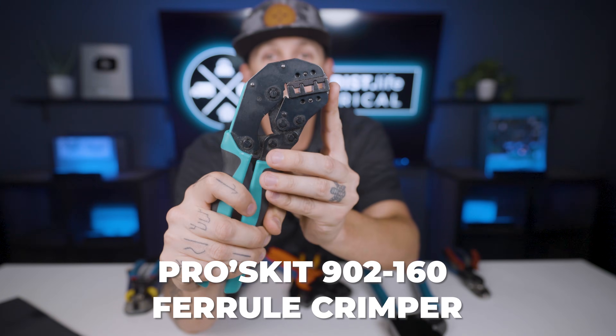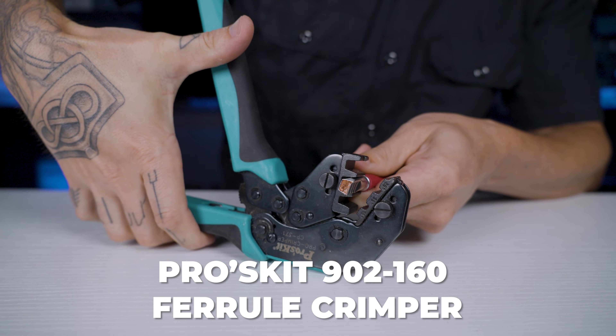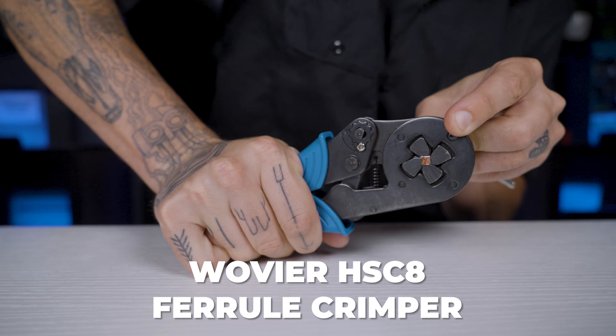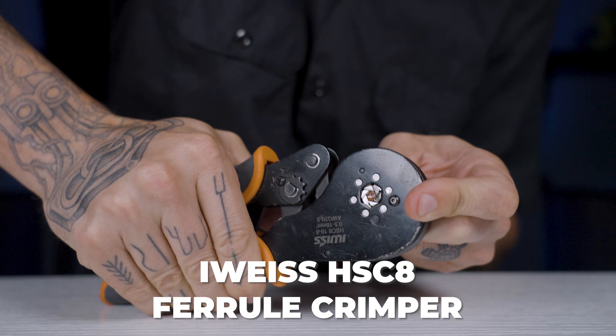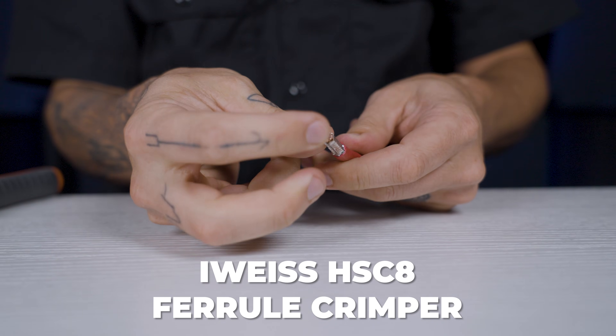Ferrule crimpers. The Proskit 902-160 ferrule crimper is for trapezoid-shaped ferrule crimps for square terminals, for wire sizes from 2 gauge to 6 gauge. The Wovier HSC8 ferrule crimper is for square crimps for square terminals, good for wire sizes 6 gauge and smaller. The iWeiss HSC8 is for hexagon crimps for round terminals, for wire sizes 6 gauge and smaller. These ferrule crimpers are mostly just Amazon brands — nothing really special — and I'll link appropriate variations in the video description, depending on which ones are still for sale.